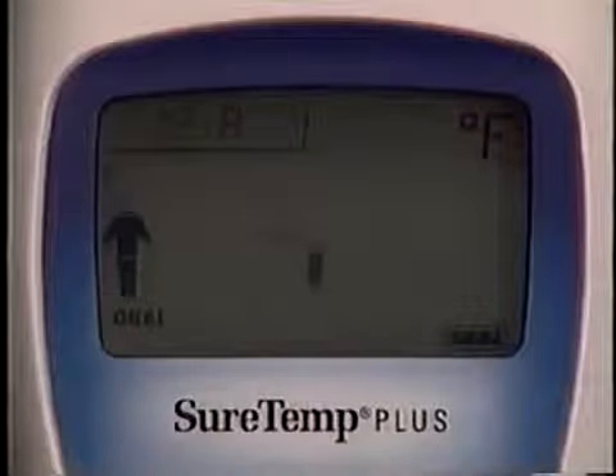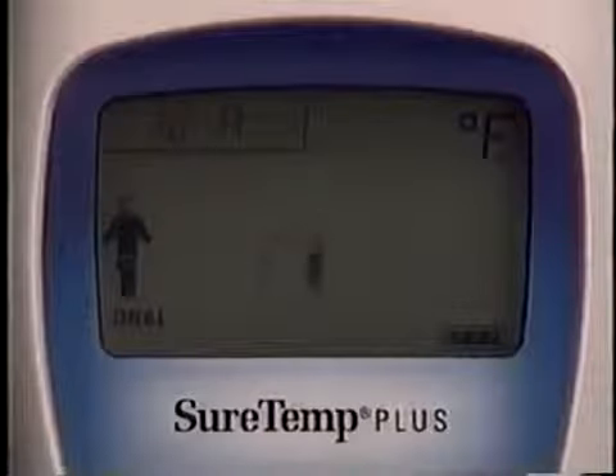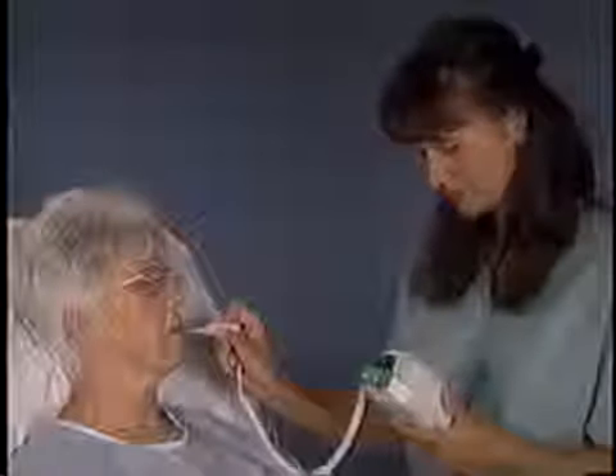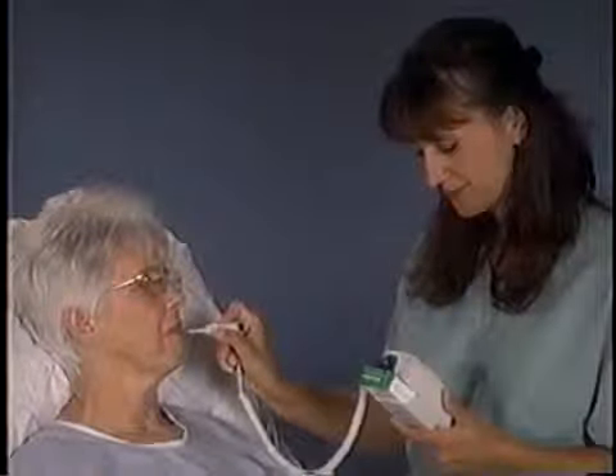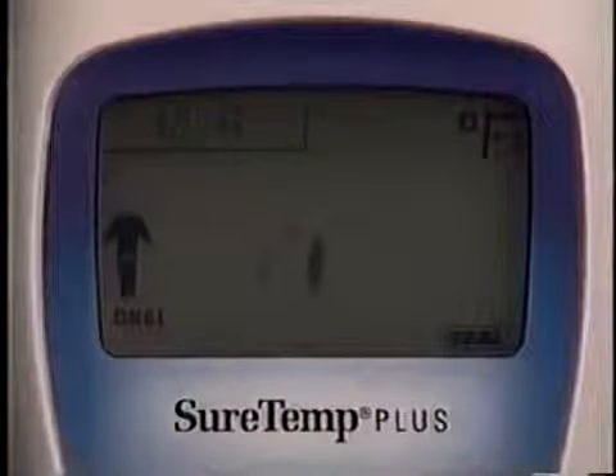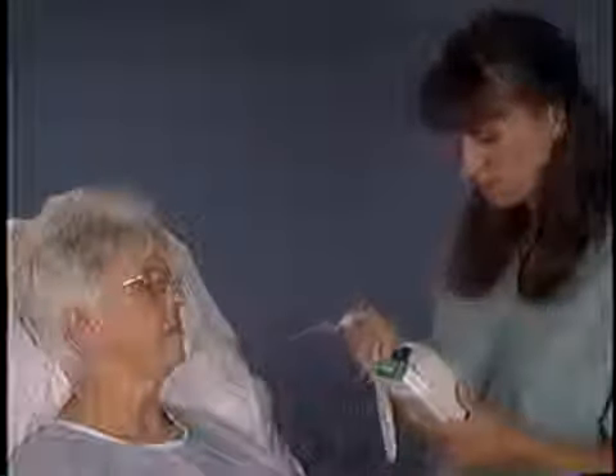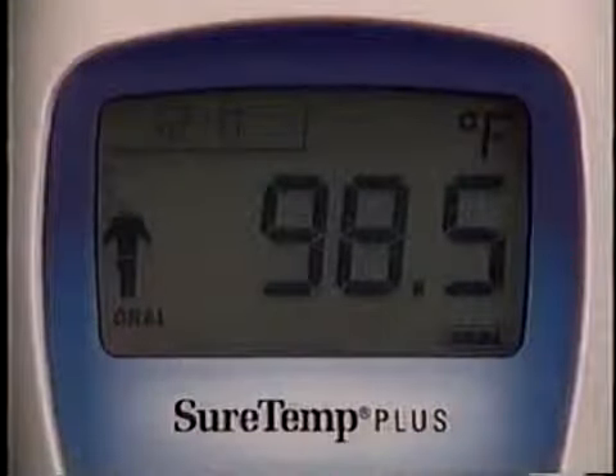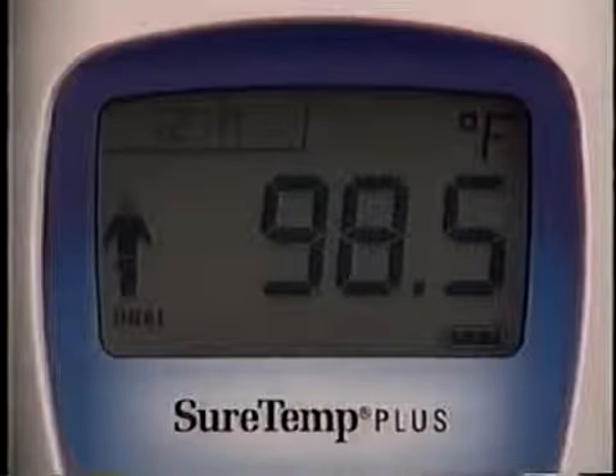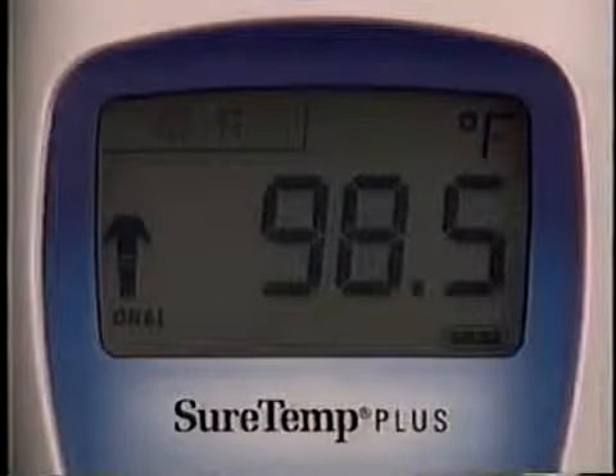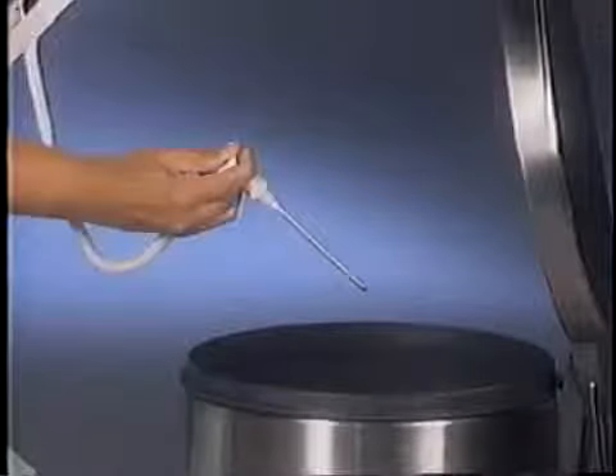Rotating walking segments appear on the display, indicating that measurement is in progress. When a final oral temperature has been reached in about 4 seconds, the unit beeps and the temperature displays. Remove the probe from the patient's mouth and note the temperature, which remains on the display for 30 seconds or until you place the probe back in the well. Eject the probe cover by pressing the ejection button and place the probe back in the well.